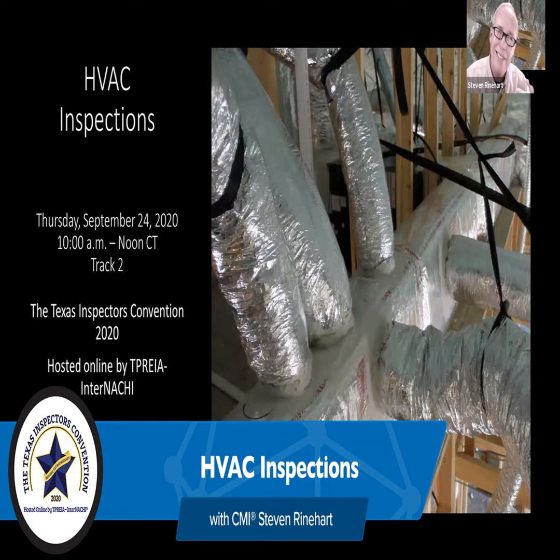Now, some guys, when they run the draft hood, there is a simple check, and we used to use these little sticks called matches. You can light a match, and I even had some smoke matches that you light, blow out, and they continue to burn smoke, and it was just for this. So if the unit's running, and you've got a little smoke generator, you run it in front, the smoke should be drawn into the draft hood and up through the flue. If it's coming the other way, we've got a problem.